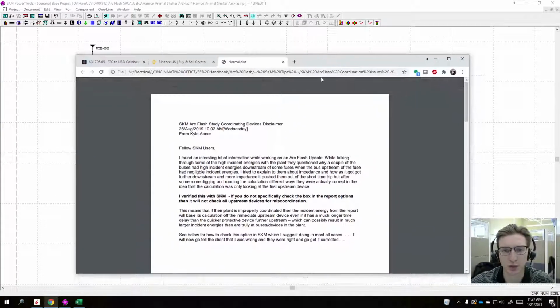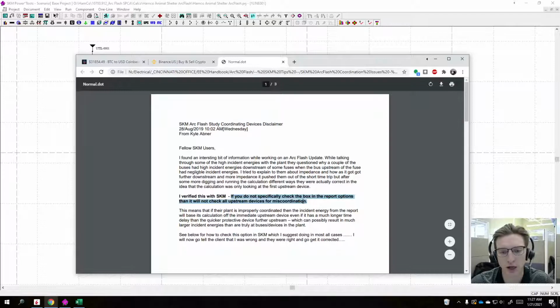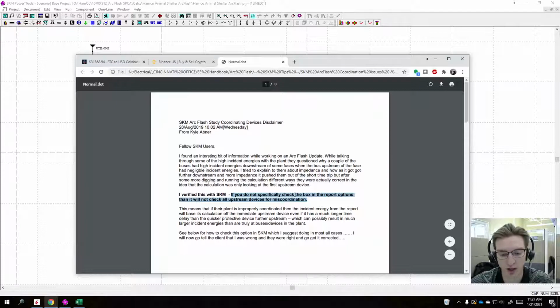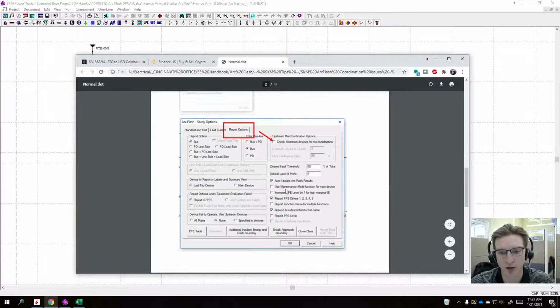Lastly, on the report options, it's very important that you check this setting. If you do not check a specific box within that setting, SKM will not determine if upstream devices could have tripped. So if you have miscoordinated devices, SKM is not going to check that without the setting. In report options, it's this box right here, and you can tell it how many upstream levels to search for.